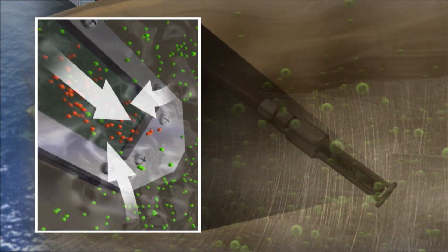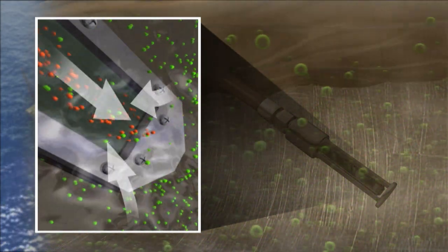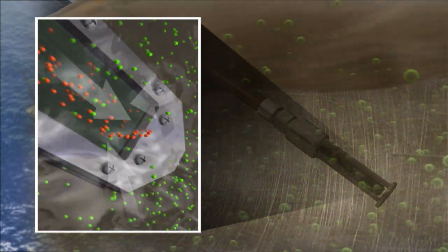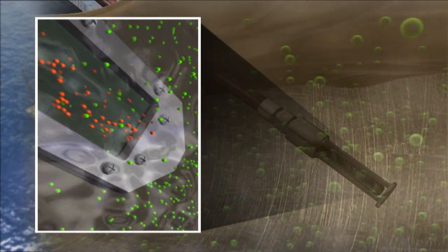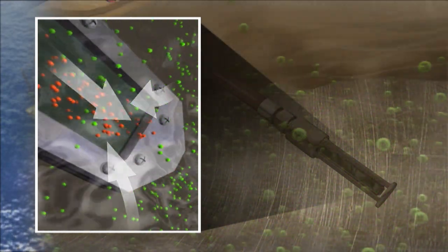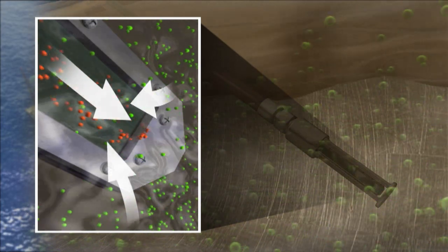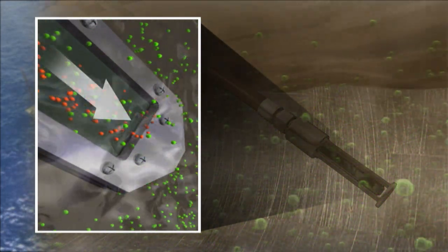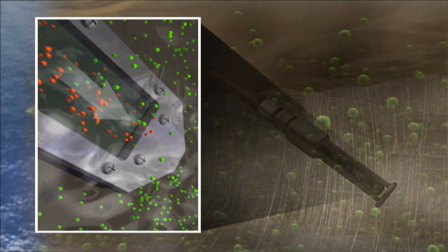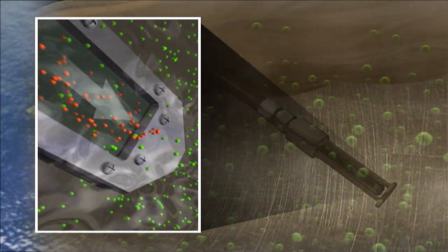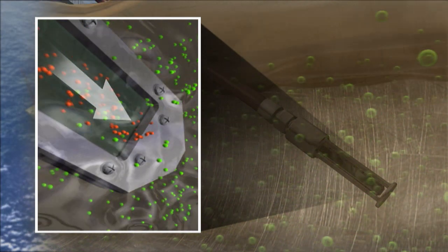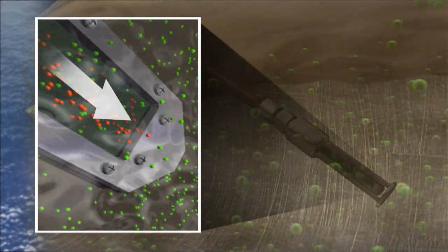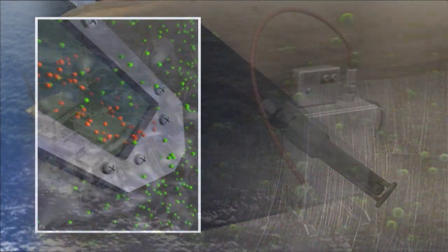This difference in pressure allows each gas component, whether free or dissolved, to permeate across the membrane. In this way, both hydrocarbons and non-hydrocarbons are extracted. A carrier gas continuously sweeps the membrane to maintain the pressure differential and transport the gas samples through the sample lines to the GCTracer's rugged explosion-proof enclosure.